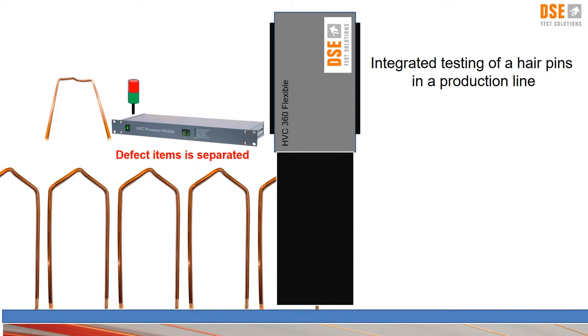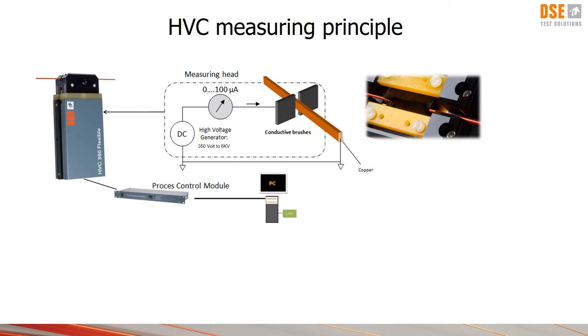Let's take a look at the measuring principle behind it. A part of the measuring head is a high voltage generator which is operating from 350 to 6 KV. The inner conductor is connected to ground and now we measure continuous current flowing from the brushes towards ground. Due to the insulation the current can only flow in cases of defects in the insulation.